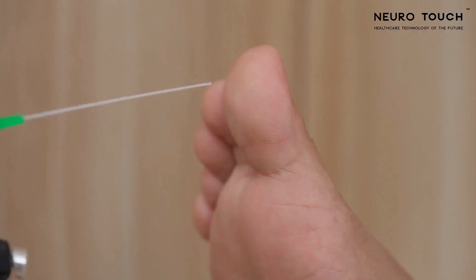data. If the patient couldn't feel the touch sensation, despite the green monofilament being completely buckled, replace the green monofilament with the blue monofilament. Reset the data and repeat the test at the same test point. If the patient still fails to feel the touch sensation, despite the blue monofilament being completely buckled, replace the blue monofilament with the red monofilament, reset the data, and repeat the test at the same test point.